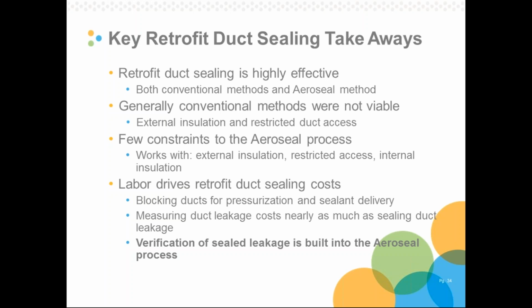Well, I should say that we observed almost no constraints with the Aeroseal process. It worked on systems with external insulation, internal lining, restricted access, dirty ductwork. There was one notable restriction, and that's that Aeroseal doesn't seal very large gaps. I think they say in their product literature that it's over 5/8 of an inch gap size. And I think it could actually seal those gaps. It's just that the time for sealing them increases exponentially. So those kinds of leaks, which we have previously said are quite rare in the grand scheme of things, are probably better off being sealed manually.